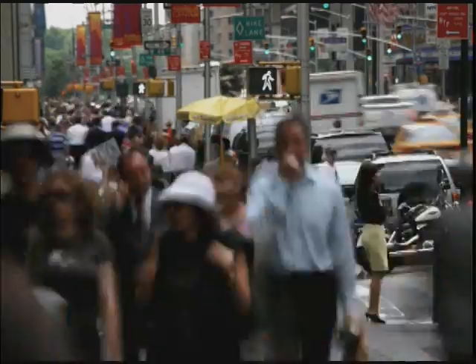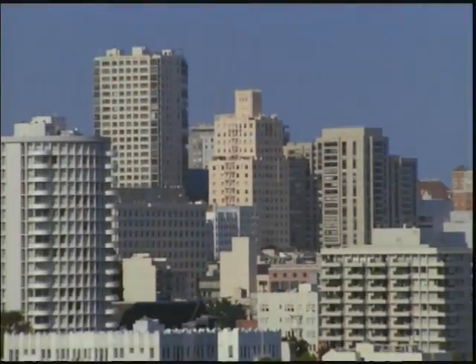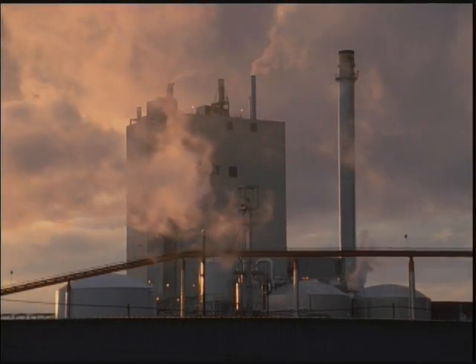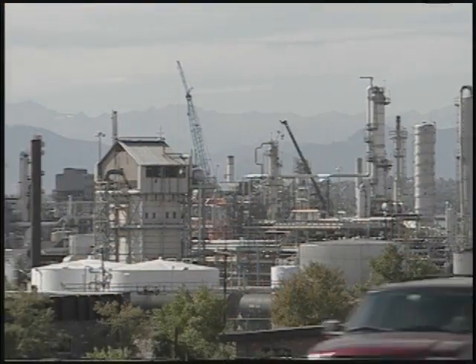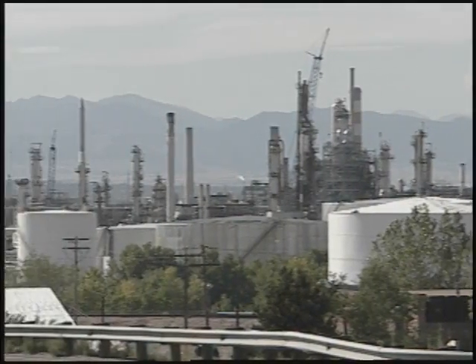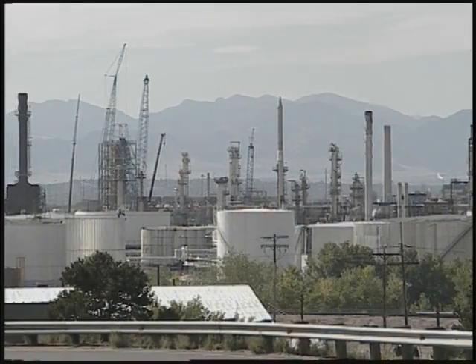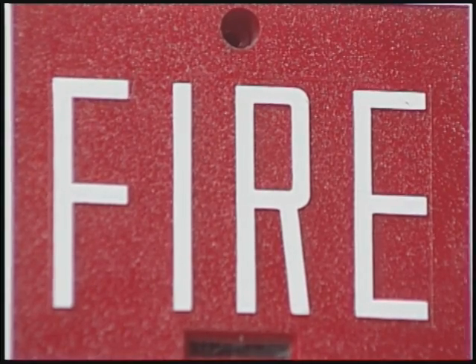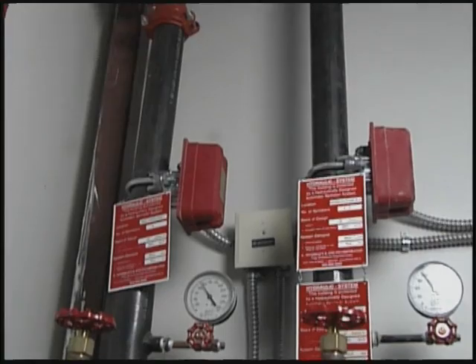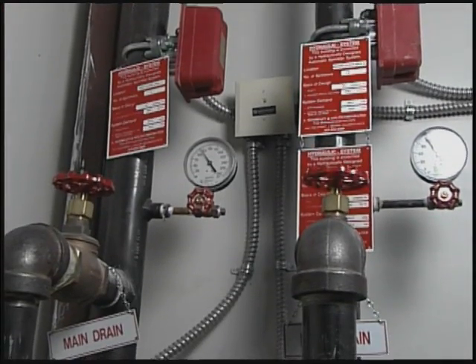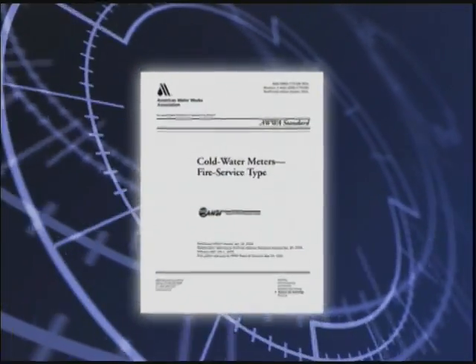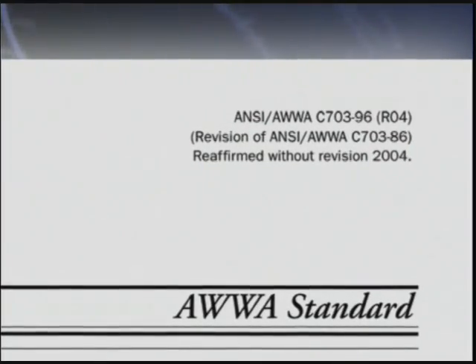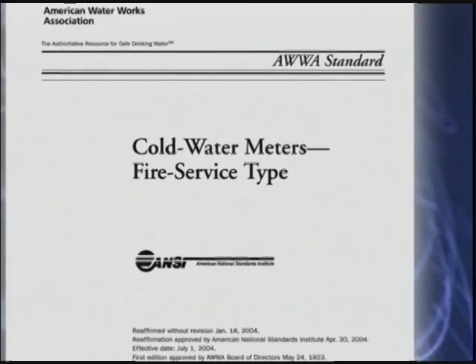Examples of customers that use large quantities of water are apartment buildings, hospitals, golf courses, large public buildings, and industries. Industries using a large amount of water are those that do a great deal of cleaning, or those that incorporate water into the manufacturing of their products. Some of these customers may require fire service meters, which are designed to allow an unrestricted full flow of water for firefighting purposes. Several styles are available and are discussed in detail in the ANSI AWWA C-703, standard for cold water meters, fire service type.